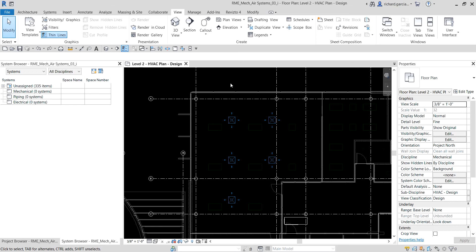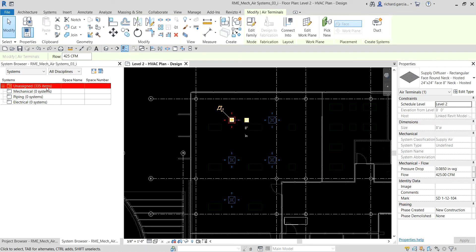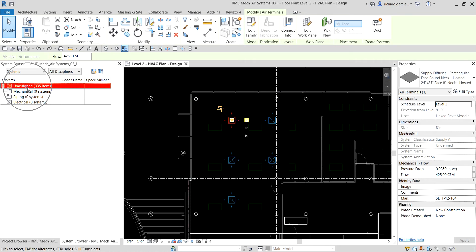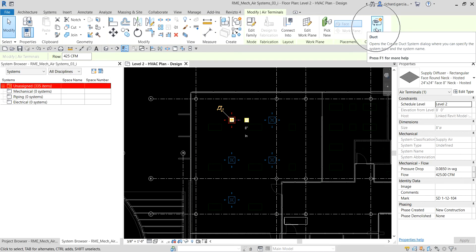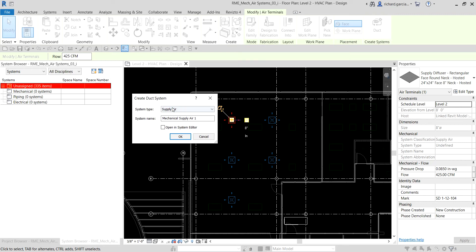To create a system without physically connecting components via ductwork, select an air terminal. On the 'Create Systems' panel, click the Duct option. You'll be prompted to create a duct system — because the connector on this air terminal is a supply connector, the system type will be 'Supply Air'.